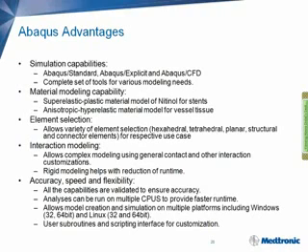Secondly, Abaqus provides us with large material model selection. Some particular ones of interest for us are superelastic plastic modeling capability of shape memory or nitinol alloy, a general hyperelastic modeling capability to model polymers and rubber components in our delivery system, an anisotropic hyperelastic model to model vessel and other tissues, and viscoelastic model to determine creep and relaxation behavior. Accurate material model helps in improving the quality of our results.